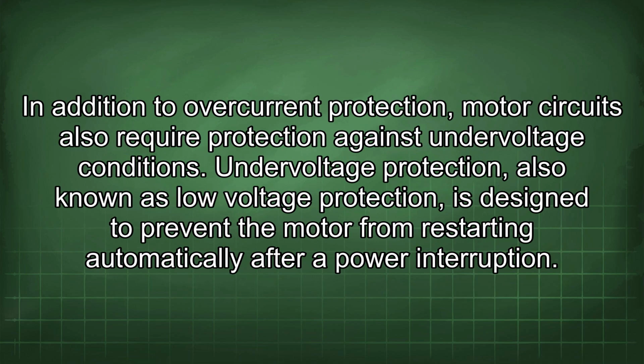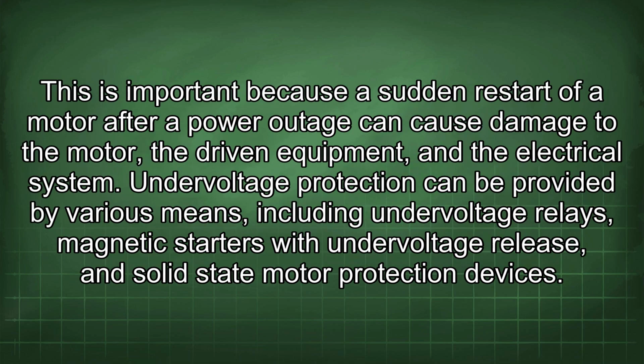In addition to overcurrent protection, motor circuits also require protection against undervoltage conditions. Undervoltage protection, also known as low-voltage protection, is designed to prevent the motor from restarting automatically after a power interruption. This is important because the sudden restart of a motor after a power outage can cause damage to the motor, the driven equipment, and the electrical system.